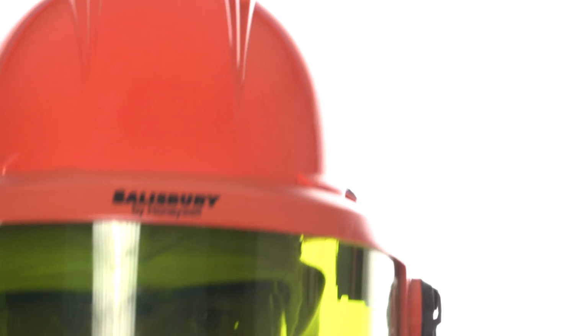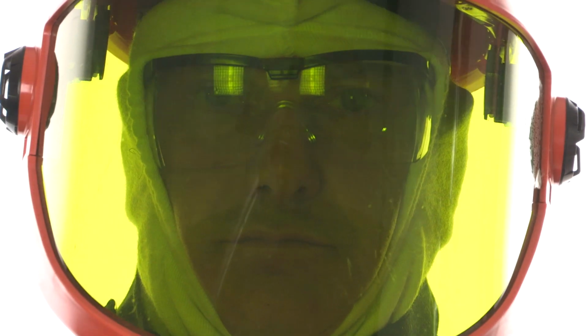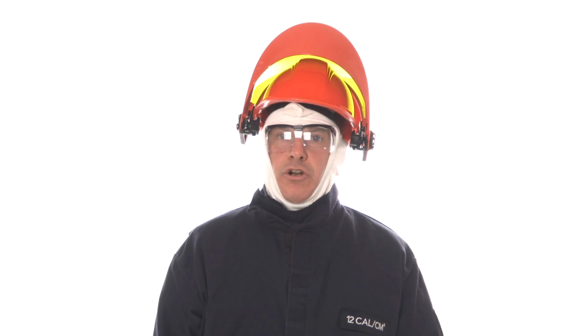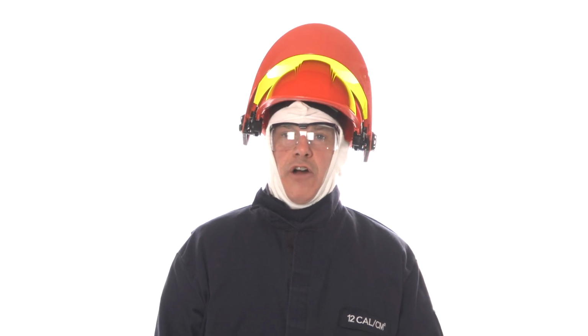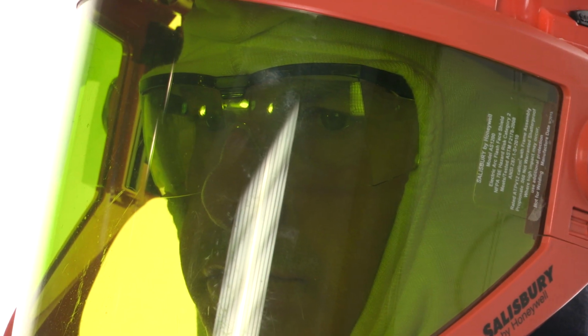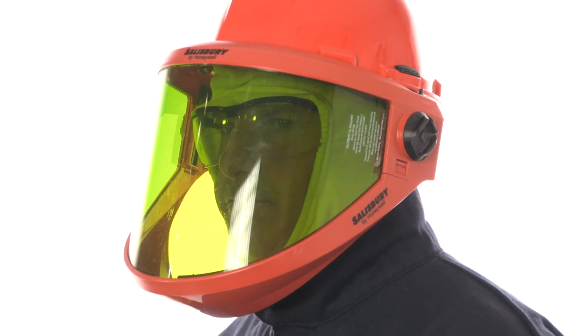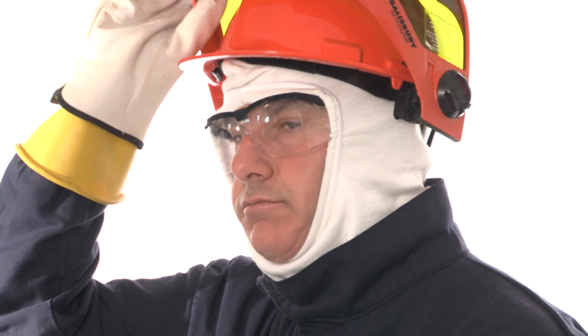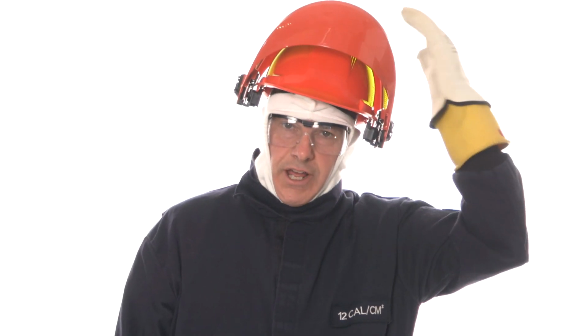The hard hat face shield combination. The face shield must be an arc rated face shield, offering protection to the worker's face from the heat or incident energy from the arc flash event, and will also offer some protection against the hot molten metal and flying shrapnel from the arc flash. The hard hat is the first and only line of defense protecting the worker's head from the flying shrapnel.